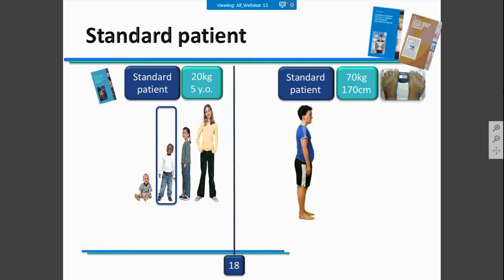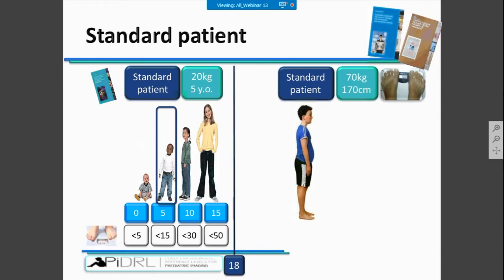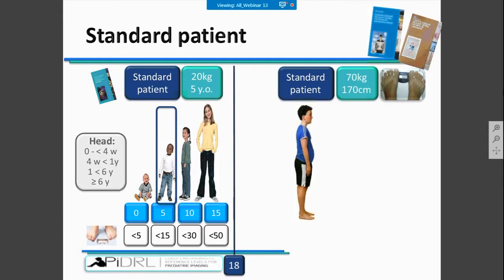Recently, there is more information about pediatric categorization, and we also have groups based on age in European guidelines. Now, using the PIDRL data, we analyzed that patients should be characterized according to patient size for body CT examinations. If you are performing head CT examinations, you must also use the age of the patients.